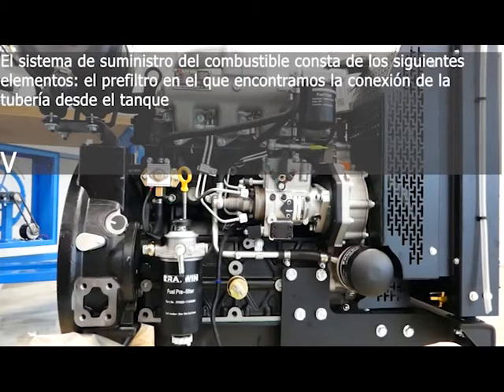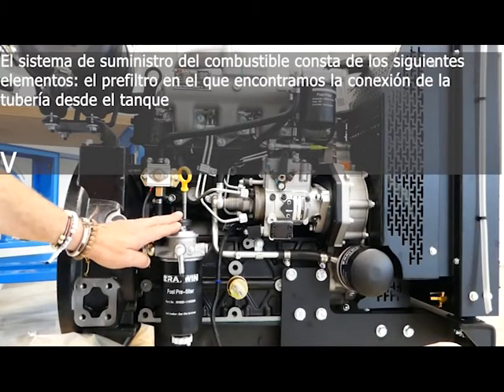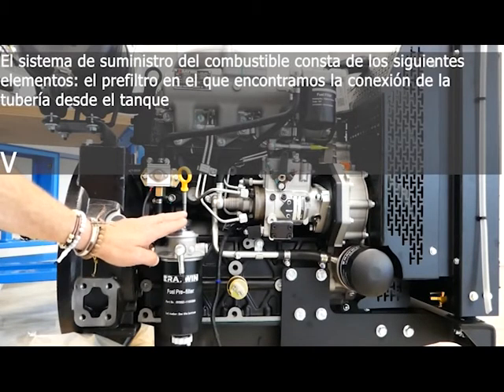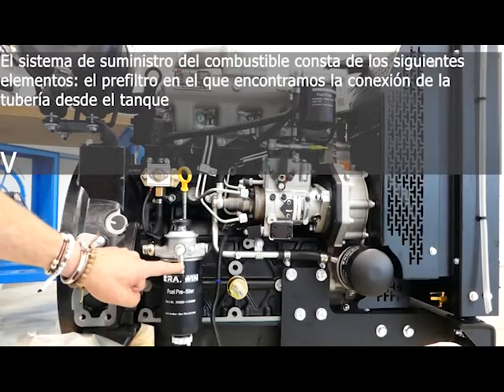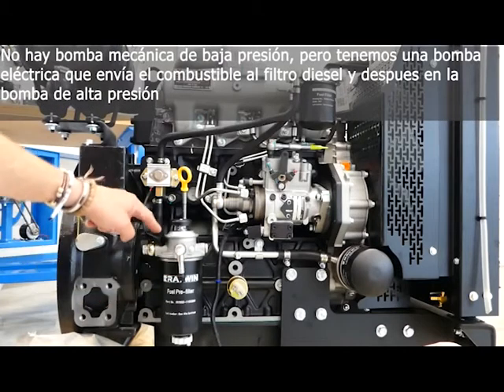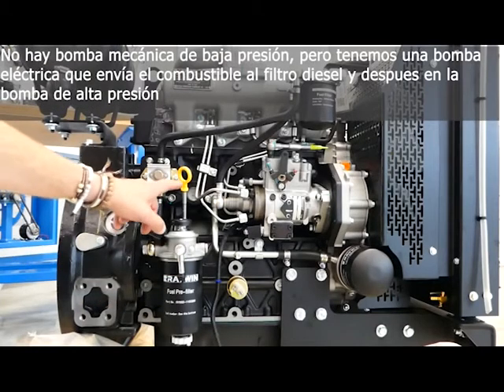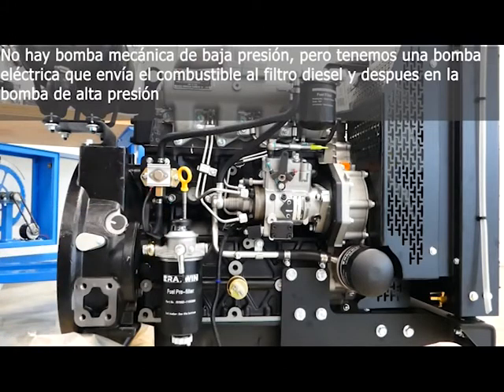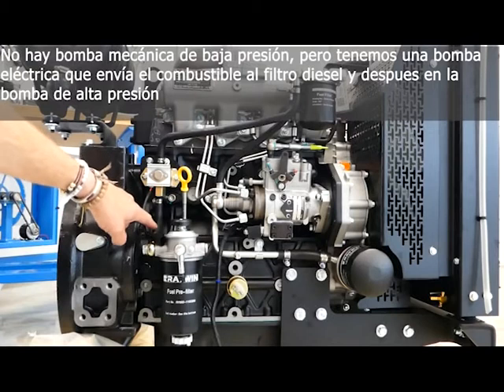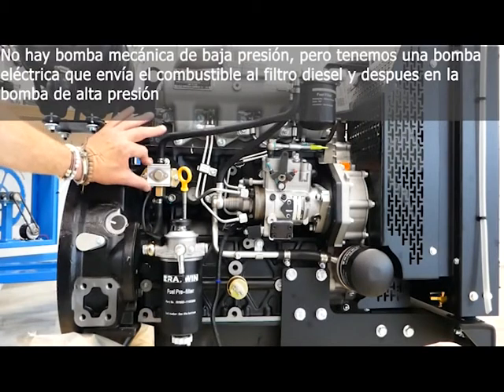Talking about the fuel system, what we have here on the RAYWIN engine. We have the pre-filter installed here in this position. This is the entry point of the fuel. Then we have a mechanical primary pump installed on the engine, but instead of the mechanical pump we can have an electrical pump here in this position.